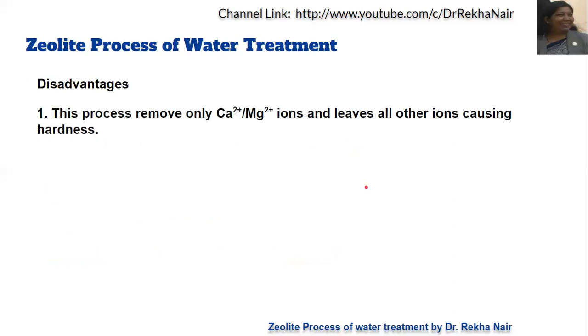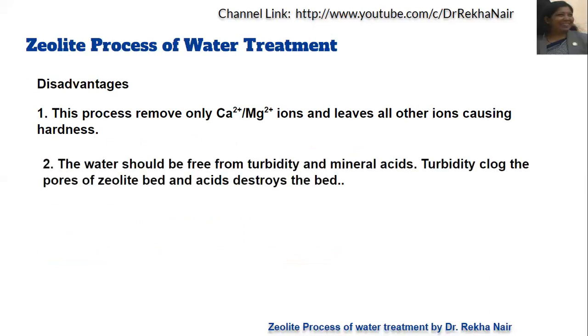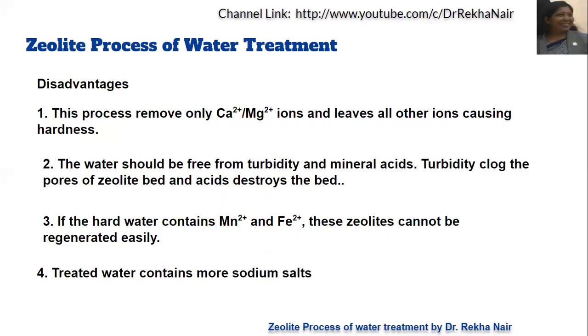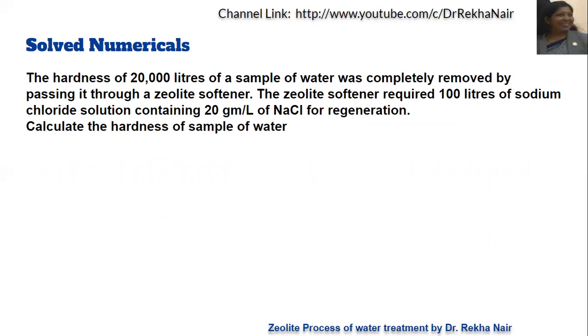There are some disadvantages as well. The process can remove only calcium and magnesium ions; all other ions are left over. The water must be free from turbidity, otherwise the turbidity will clog the pores of the zeolite bed. Mineral acids must also be absent, as acid can destroy the bed. In the case of lime-soda, there were no such problems. Additionally, if the hardness-producing ions include manganese and iron, the corresponding zeolites formed cannot be regenerated easily, making regeneration difficult. The treated water also contains more sodium salts.